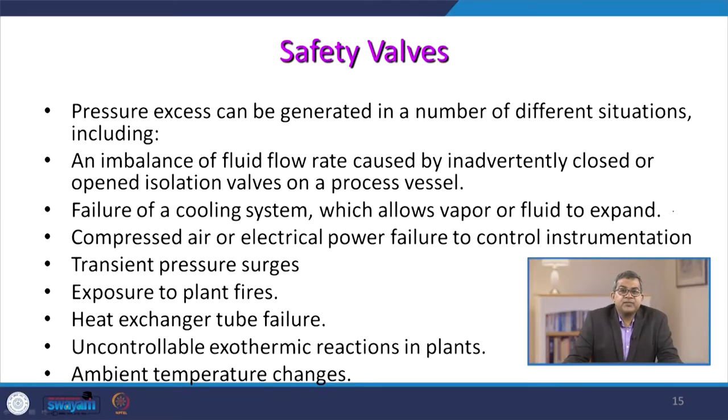Excess pressure can be generated in a number of different situations, including: imbalance of fluid flow rate caused by an inadvertently closed or open isolation valve on a process vessel; failure of a cooling system which allows vapour or fluid to expand; compressed air or electrical power failure to control instrumentation; transient pressure surges; exposure to plant fire; heat exchanger tube failure; uncontrollable exothermic or thermal runaway reactions in the plant; and ambient temperature changes.